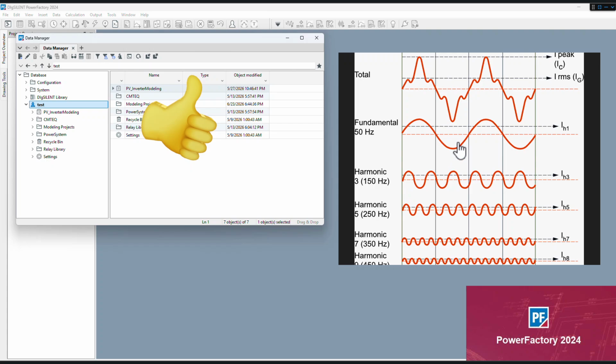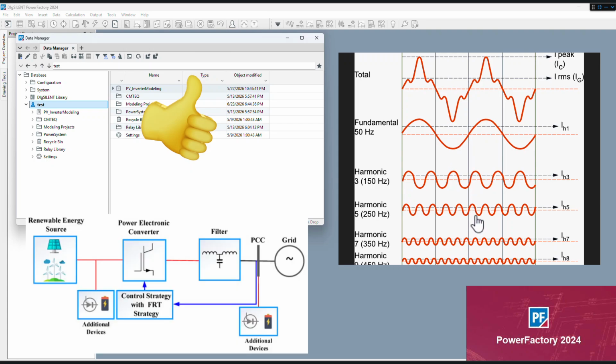They are mainly produced by non-linear loads, which I explained in that tutorial, part 1 mostly, and part 2, such as variable speed drives, rectifiers, UPS systems, LED lightings, and many modern power electronics converters. Basically, systems that have to do with switching cause these peaks and distortions of the current that no longer follows the fundamental current, so it causes harmonics.